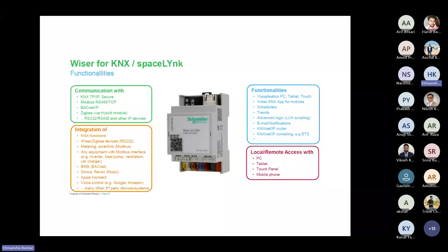So this is the basic wiring diagram showing how these things are connected with the main controller. Via IP, we can connect the BACnet devices, the Modbus devices. We can integrate the BMS system, getting our home or office system integrated with the lighting control system. The AV system - if you have a projector or AV units - that can also be controlled via this controller, with a single point of control.